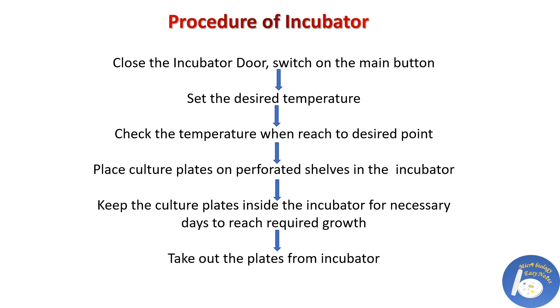The procedure for using the incubator is: close the door of the incubator and switch on the main button, set the desired temperature, check the temperature when it reaches the desired point, then place the culture plates on the perforated shelves inside the incubator. Keep the culture plates inside for the necessary number of days to reach the required growth, and after growth is achieved, take out the plates from the incubator.